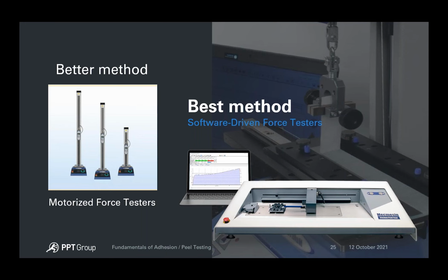And then you also have the additional advantage of exporting the raw data, so you can create additional calculations or cataloging or creating reports and so on. In any case, a software-driven tester offers you the best opportunities for repeatable and consistent adhesion strength measurements. So these are the tools that you would usually use in peel and adhesion test applications.